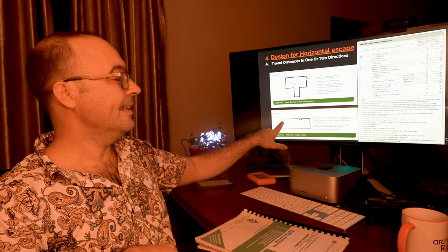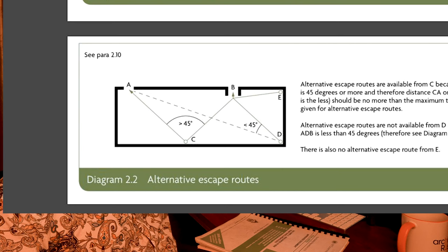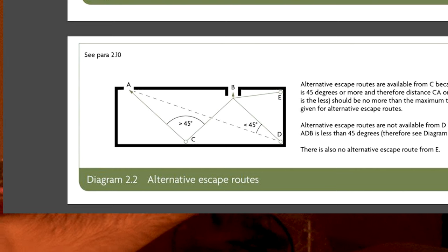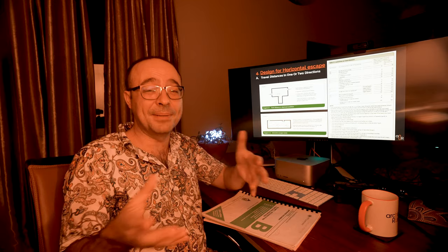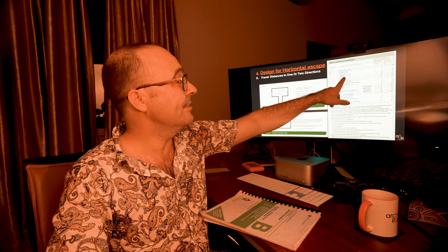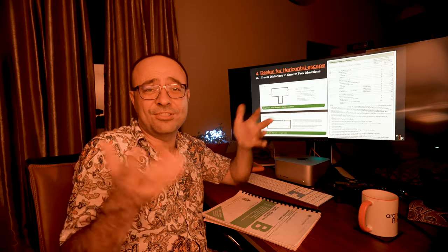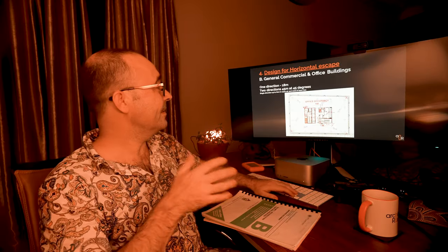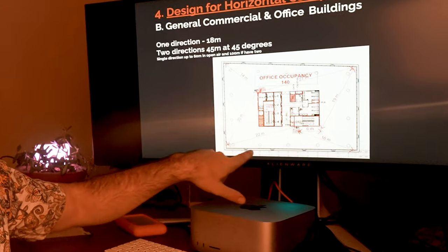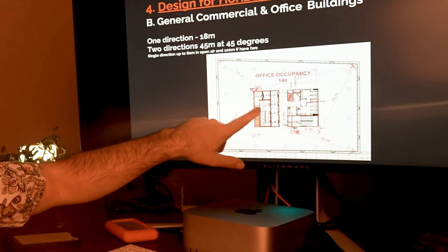You can see in this diagram here you've got 45 degrees for two fire escapes, but there's one escape here — obviously there's no 45 degrees, so that'll be 18 meters to that escape. That could be up to 45 meters with two escapes. This changes a little bit depending on the purpose group — there's table 2.1 that tells you the distances. But generally this is for most commercial buildings. This is an office building: everything's 18 meters to one escape stair, or 45 meters and 45 degrees to two escape stairs.